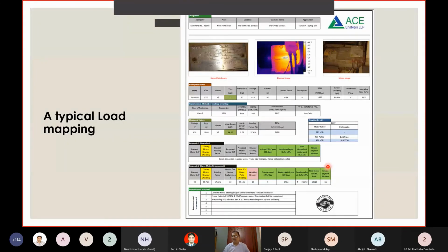We do this normally for medium and large size motors which are 11 kilowatt and above. Similarly, we also do a lot of load mapping and recommending to the customer. This is Mahindra Nashik plant. Just take a look at the layout of this report. You will get a lot of information here, very useful information. We take a normal picture and a thermography picture. We put the nameplate, and then we go on to nameplate details.